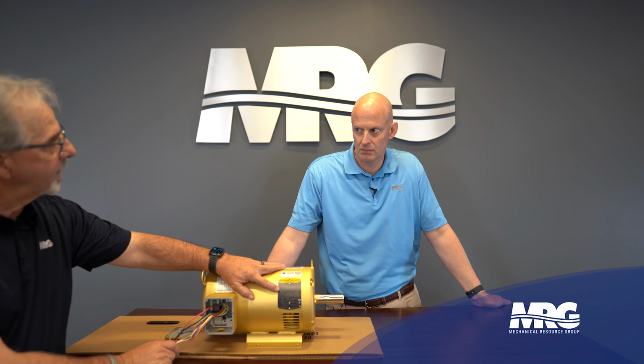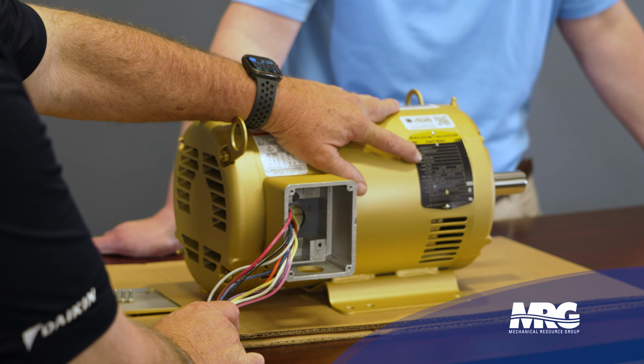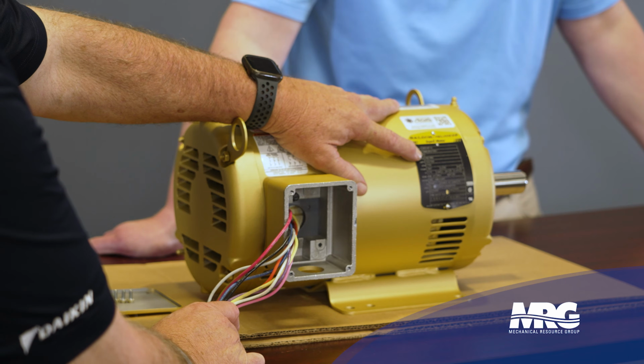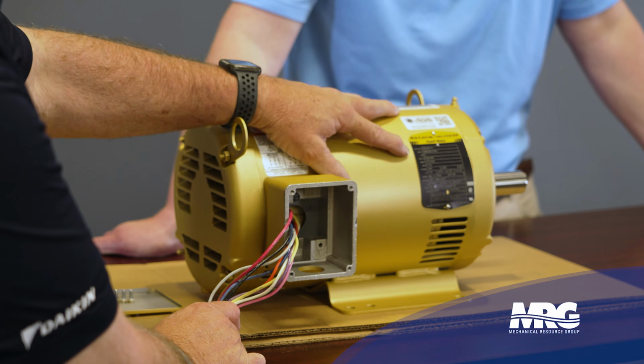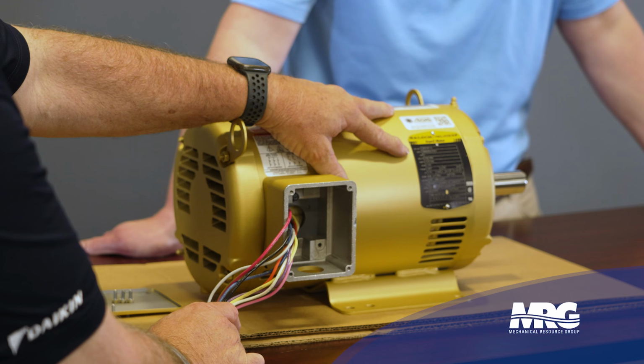On here is your rating. It's going to give you your horsepower rating, the amount of current that the motor is capable of. So that right there is the pertinent type of information that you need to have.